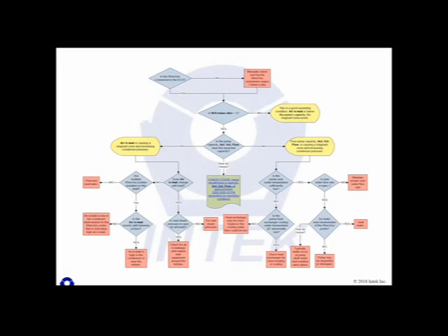And now I've linked that to measurements that can actually be made with the RheoVac tool, the water to air mass ratio. And I've stated that it's the most important parameter because that water to air mass ratio is proportional to the number of tubes being shut off from condensation. It's directly proportional to the performance of your condenser as related to air in-leakage or vacuum pump problems. And so when you go to troubleshoot and if you have a RheoVac, the very first parameter you should go to is the water to air mass ratio. That will tell you immediately if there is an issue.